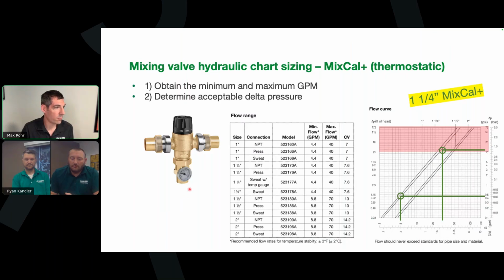So that would have a minimum flow rate of 4.4 GPM to make sure that you're not hunting at that low flow rate. So we've got 5, so we'd be in good shape there.